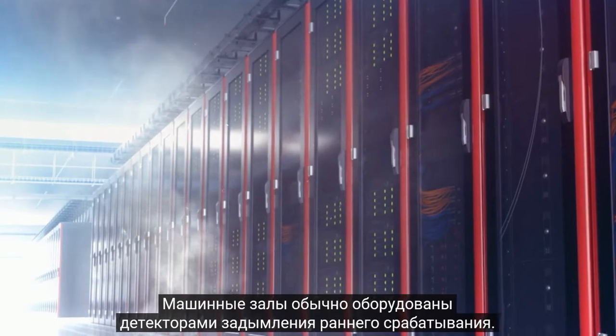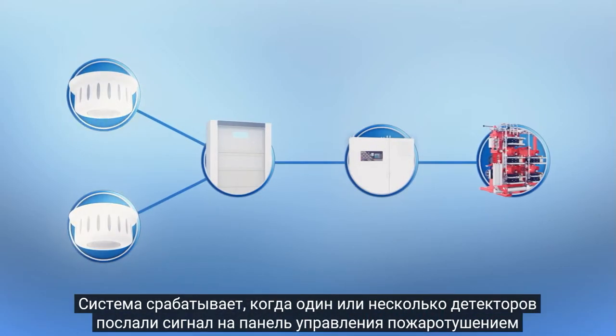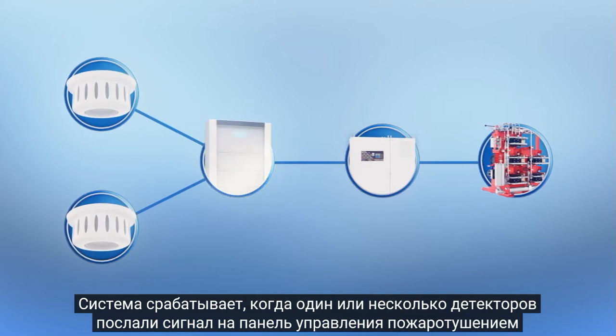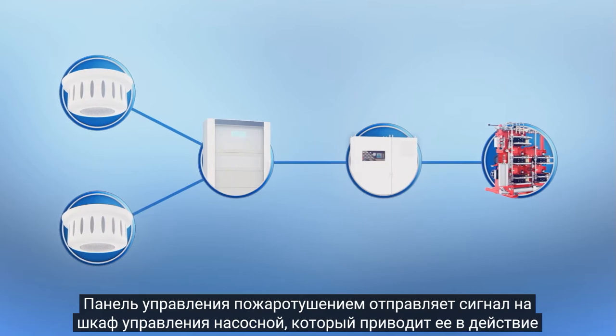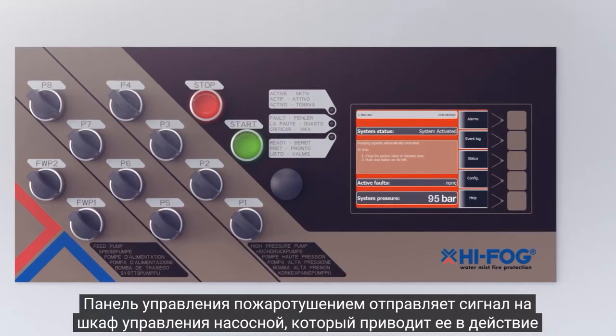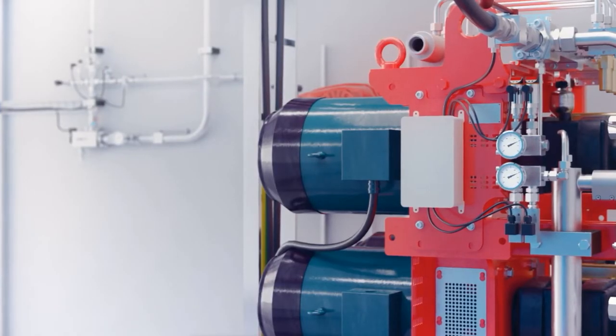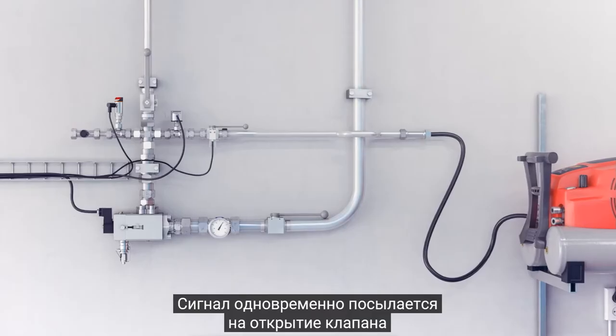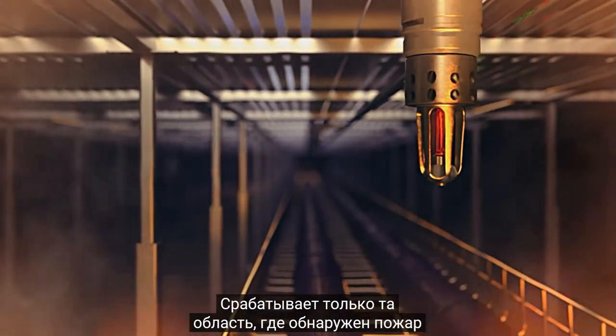The data hall is typically equipped with early sensing smoke detectors. The system activates when one or several detectors send a signal to the release panel. The release panel responds by sending a signal to the control cabinet, which immediately starts the Hi-Fog pumps, which then will generate high pressure. A signal is also sent to open up the valve, and water mist is only released to the area where it is needed to fight fire.